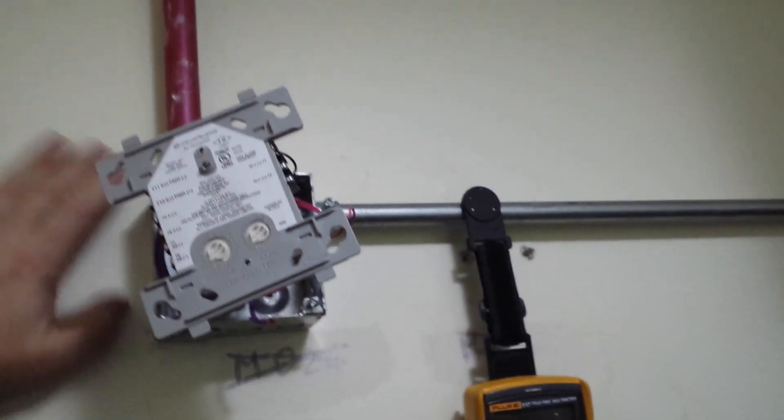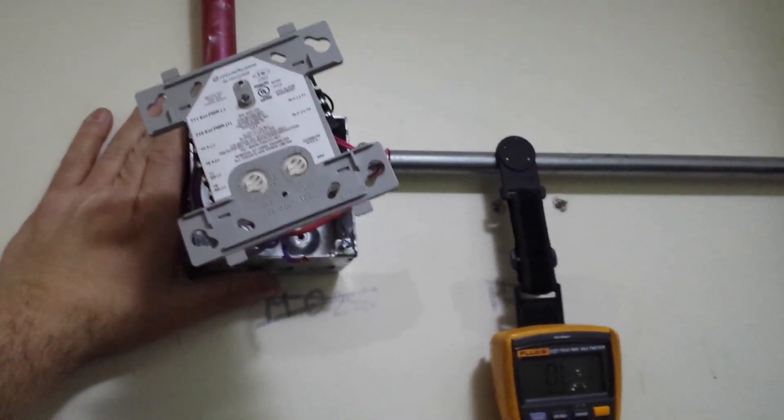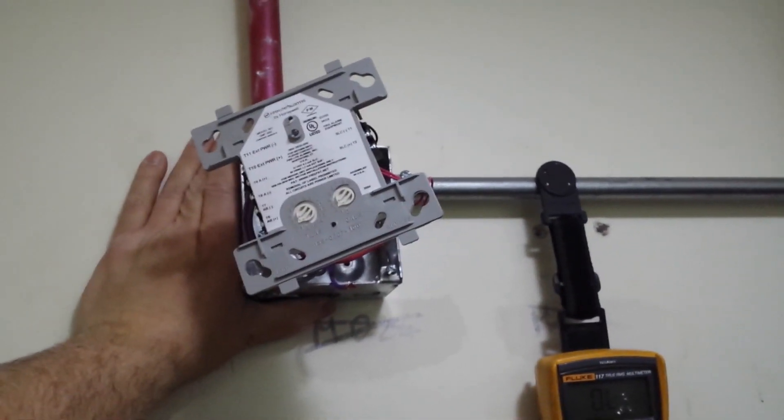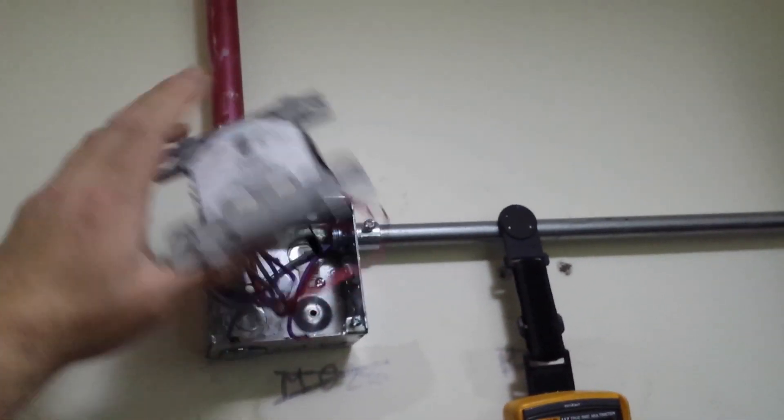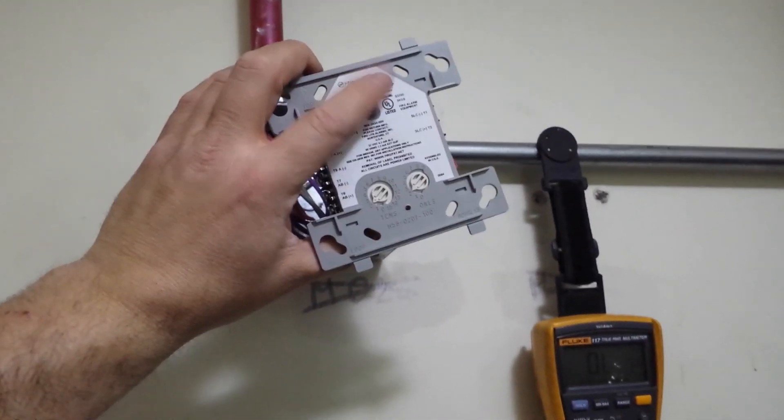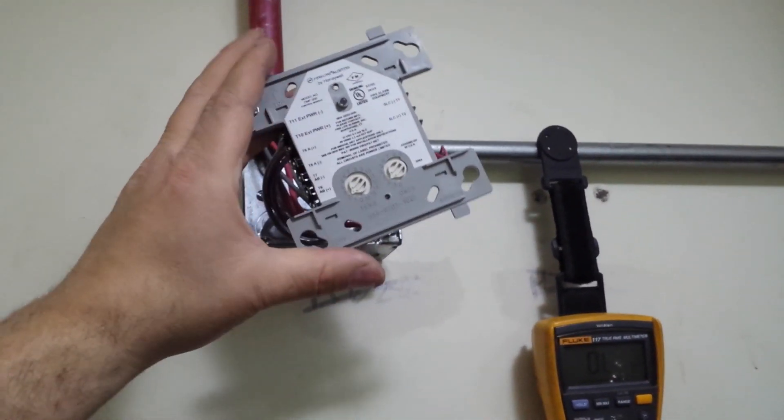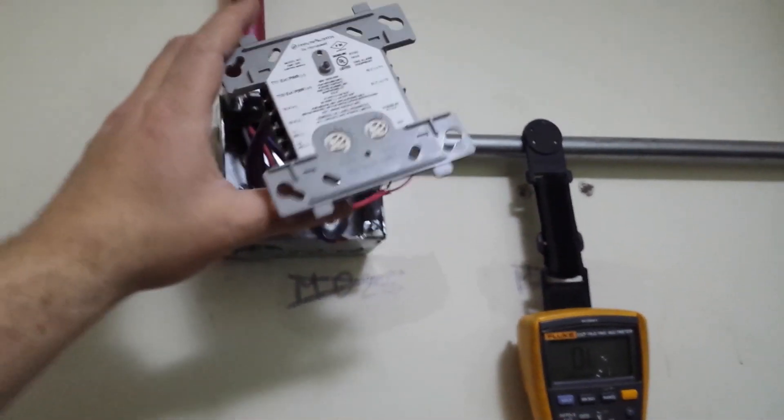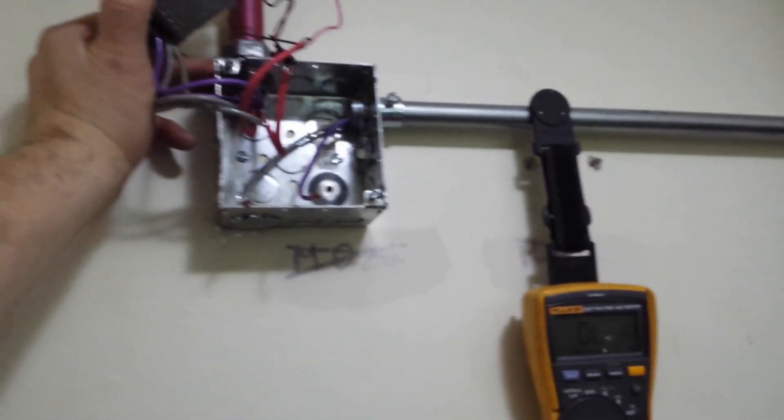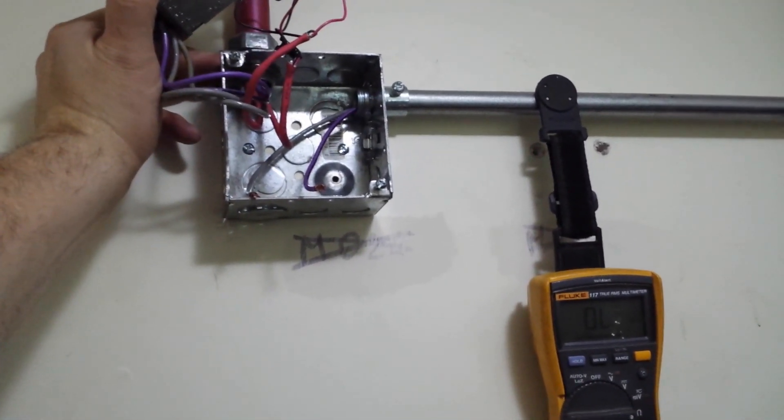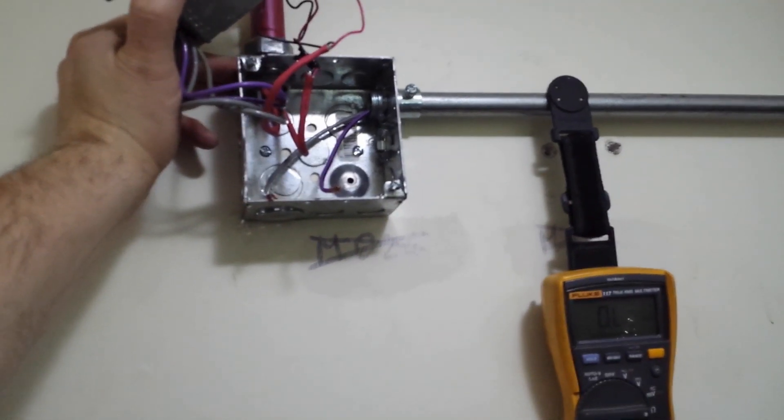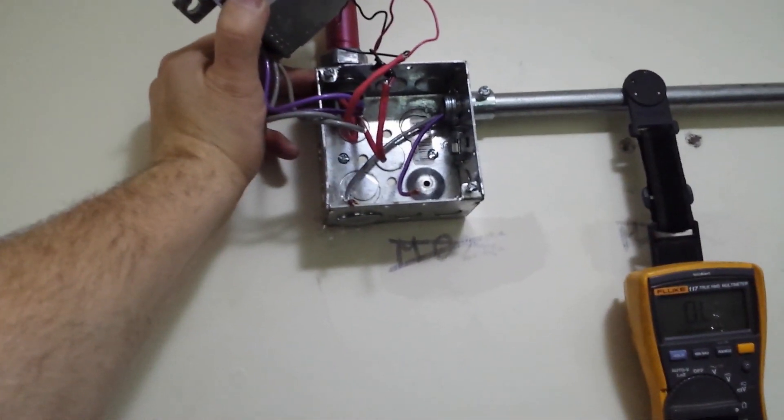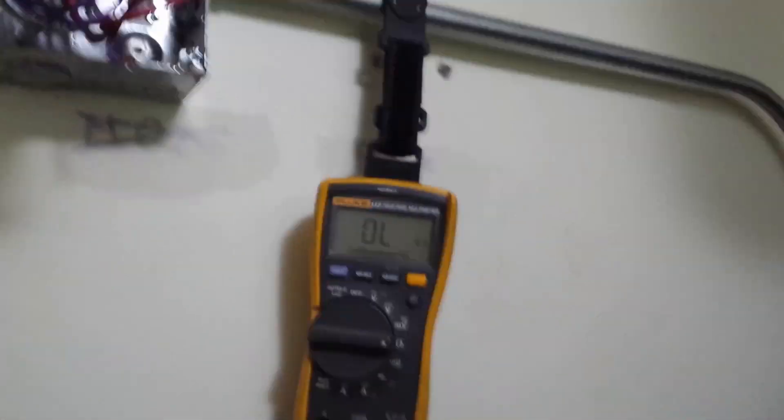I found that when I disconnected the SLC from this module, everything else in the system seemed to be working. This was the only trouble spot. This time, then I disconnected the output side. Here's the output wiring that goes, in this case, to an outdoor strobe. Disconnected, reconnected the SLC, and we've got signal on here. So the SLC now seems to be working.